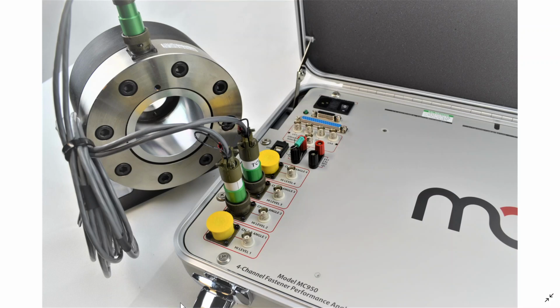In this video, I'm going to show you how to connect a torque tension cell to the MC950 and perform the calibration. A torque tension cell can measure tension or load and thread torque. There are two signals that come out of the connector on top of the torque tension cell, and they split off to two separate channels. We normally connect tension to channel 2 and thread torque to channel 3.